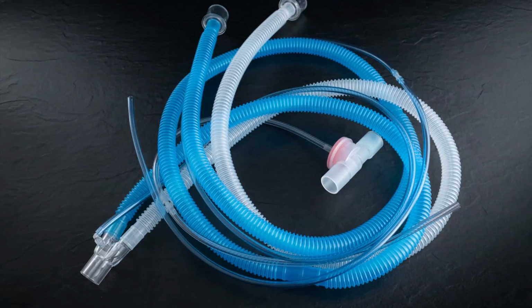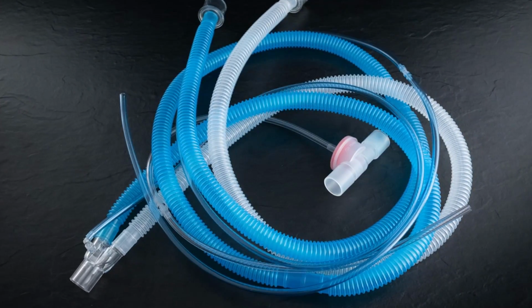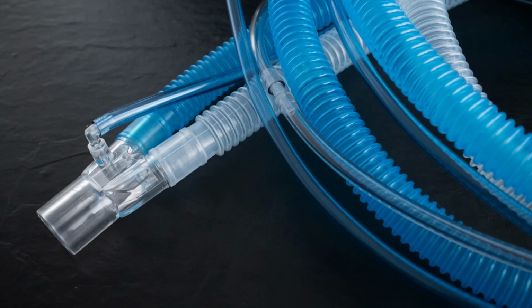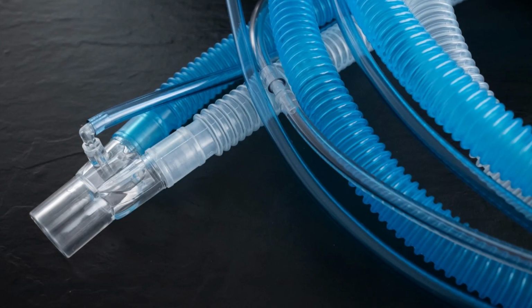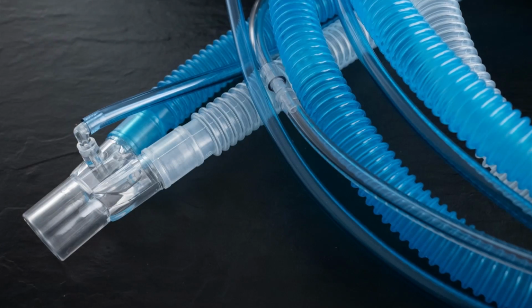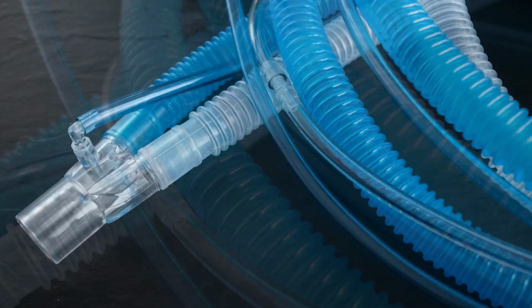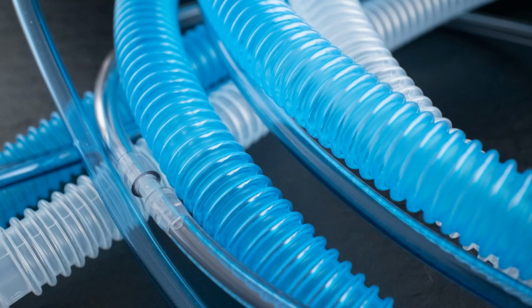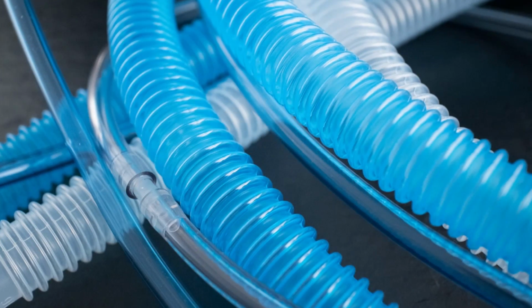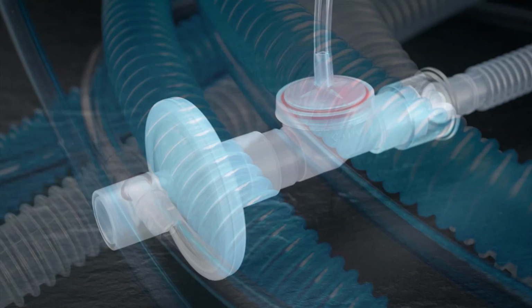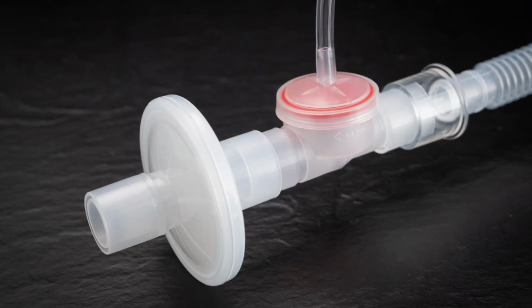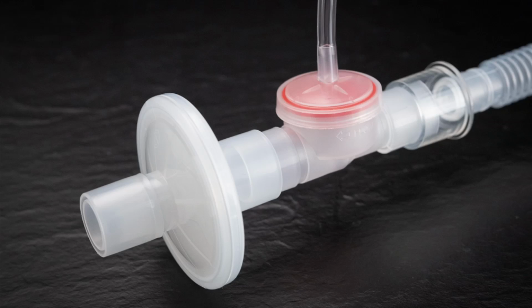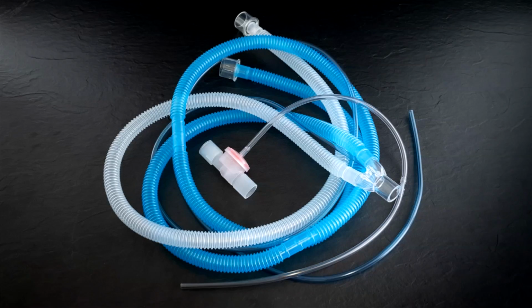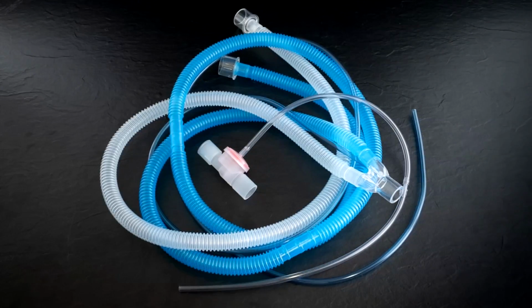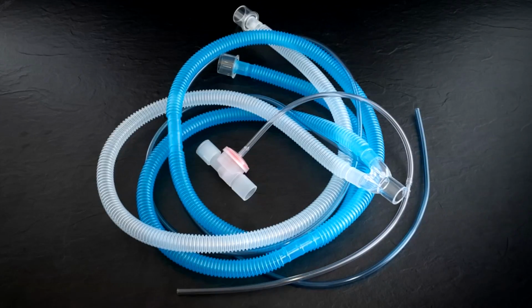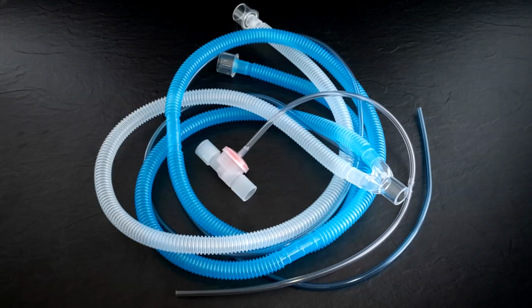The patient circuits designed for use with the Newton Mini ventilator are neonatal to infant patients, 10 millimeters internal diameter, recommended for use at 6 or 8 liters per minute flow setting. Infant to pediatric patients, 15 millimeters internal diameter for use at 8, 10, 15, or 20 liters per minute flow setting. Airon offers patient circuits in a 6-foot or an 8-foot length. The 8-foot patient circuit is particularly advantageous in an MRI setting.